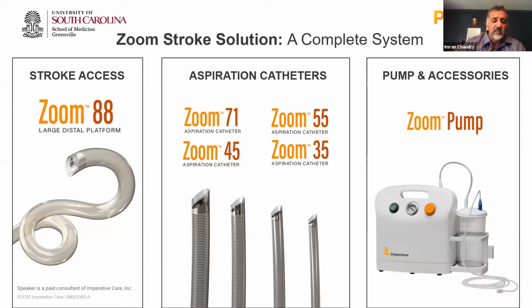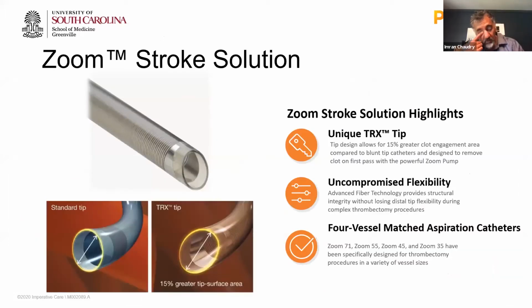The 71 is intended for aspiration of large vessel occlusions in the carotid terminus, the M1, as well as the M2. The 55 and the 45 are intended for use in mid-sized vessels. And then the 35 for distal vessels, as well as to provide support to navigate your other catheters to the target vessel. The Zoom pump currently generates the highest vacuum pressure on the market. So it's a nice complete system. In addition, the pump is actually quite quiet, so you can actually talk to your colleagues during the case without a lot of disruption. The Zoom catheter system was designed with this bevel tip.